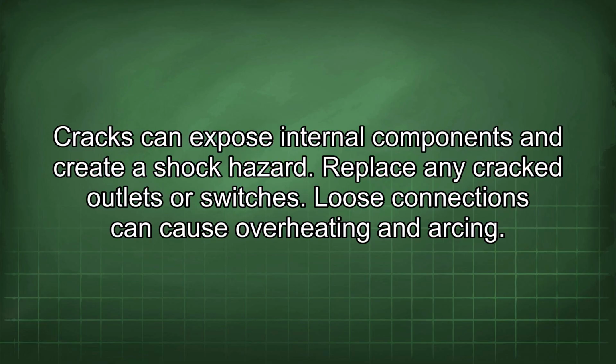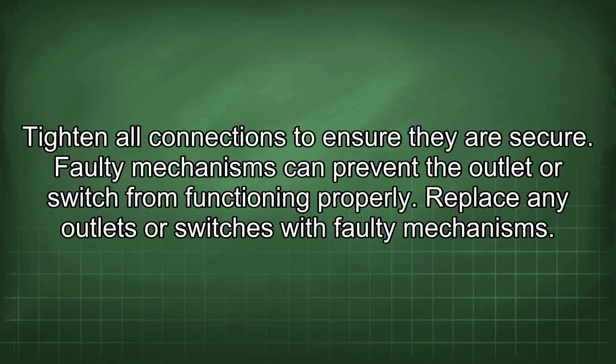Loose connections can cause overheating and arcing. Tighten all connections to ensure they are secure. Faulty mechanisms can prevent the outlet or switch from functioning properly. Replace any outlets or switches with faulty mechanisms.